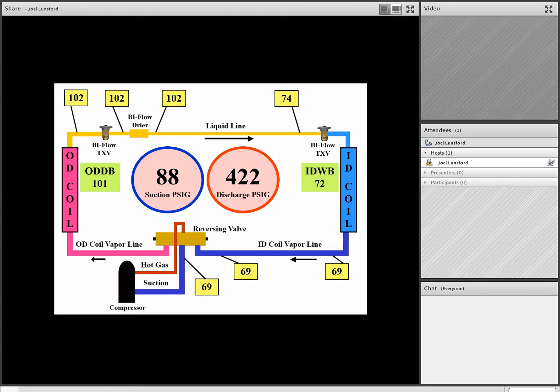At 88 pounds of suction pressure, we see that we have a pressure temperature conversion of about 25 degrees, but the temperature leaving on the cold vapor line from the indoor coil is 69. So the difference between 25 and 69 is about 45 degrees of superheat. So our suction pressure is low, liquid pressure is high, subcooling is elevated, superheat is high. So what would give us low suction and high superheat? That's the key.